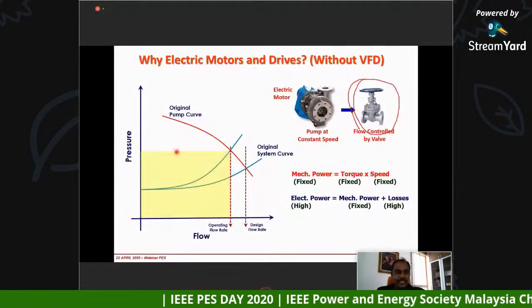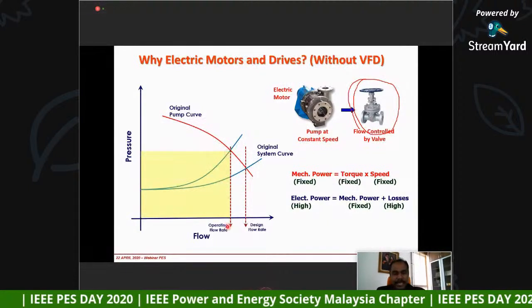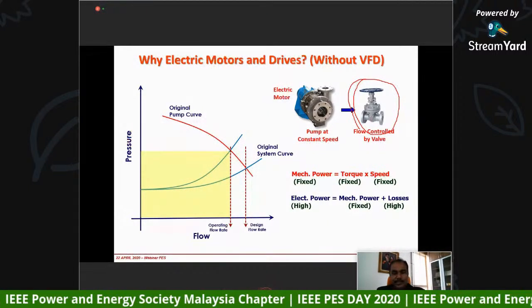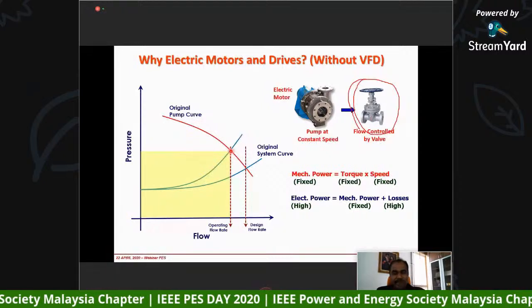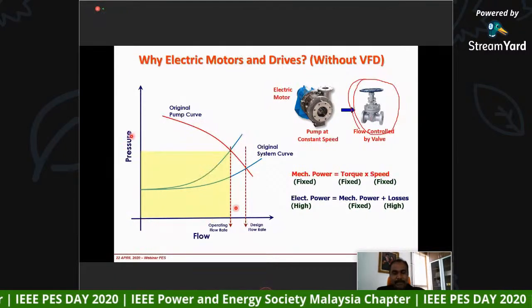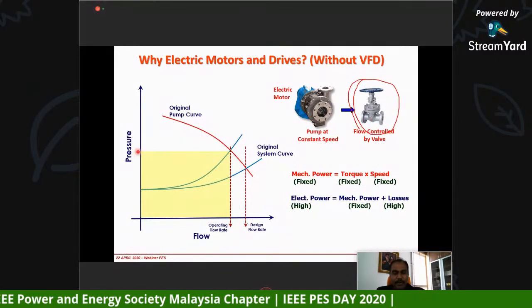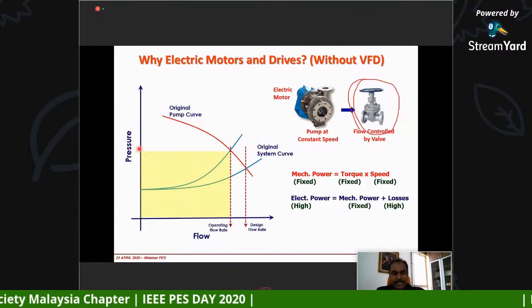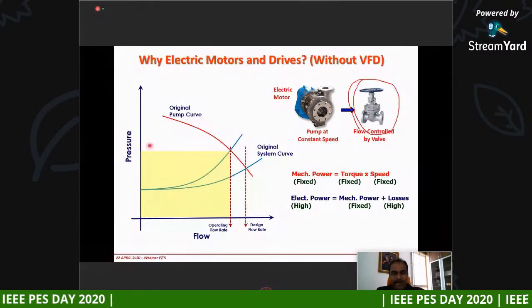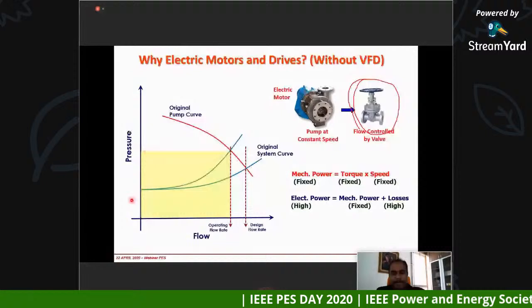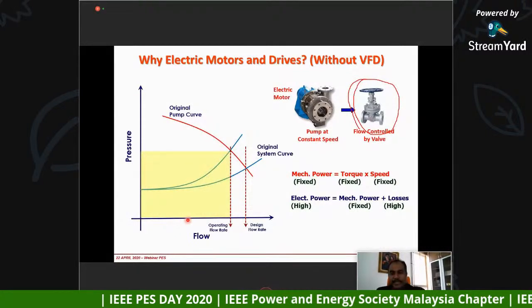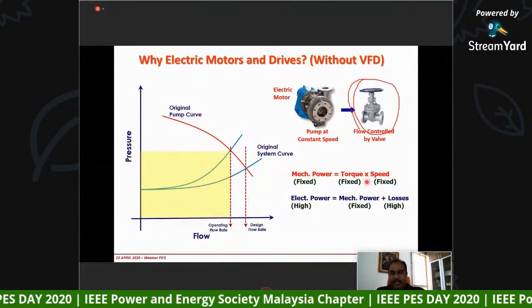So this is the pressure, this is the flow, and it's proportional to the power. The mechanical power developed by the pump system is going to be proportional to pressure and the flow. So the shaded part here is actually this area for the power. Okay. So we know that mechanical power is given by the torque and the speed.